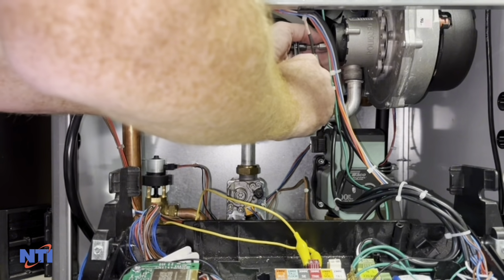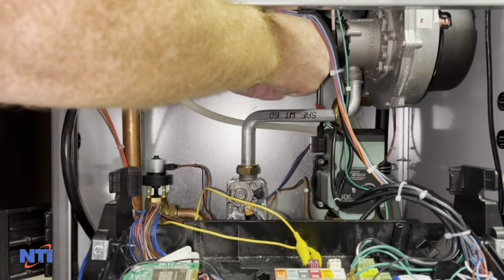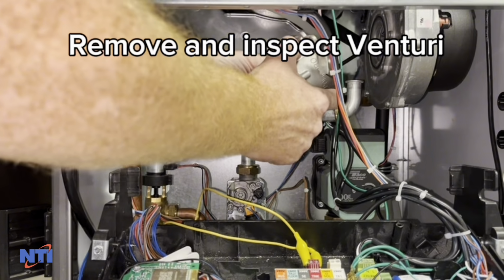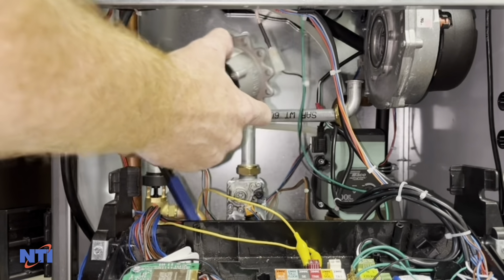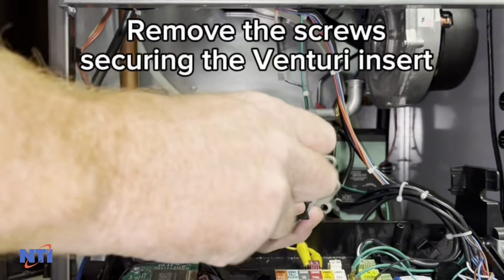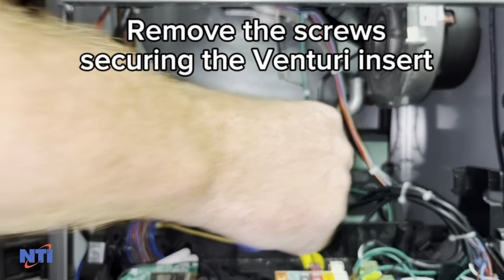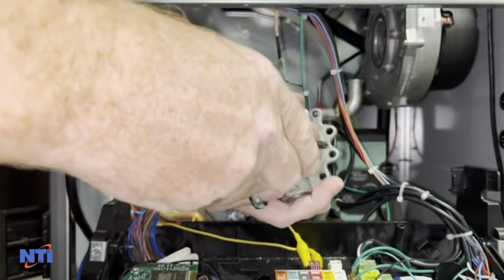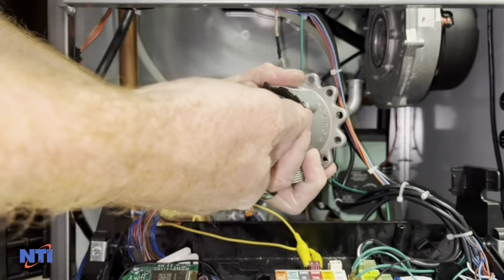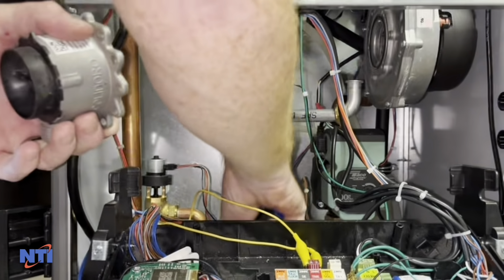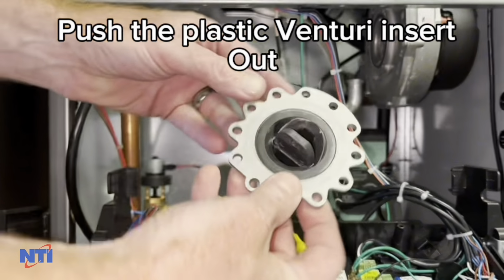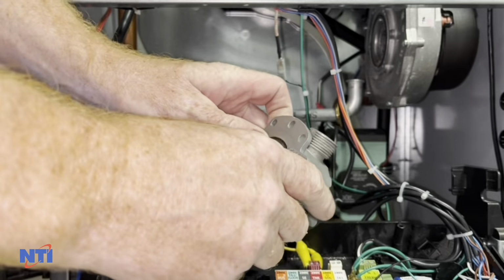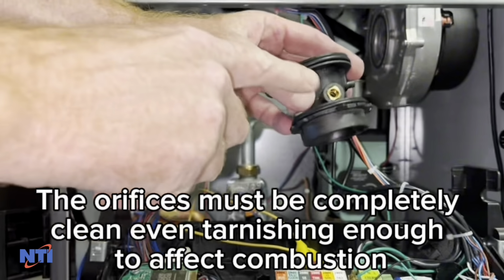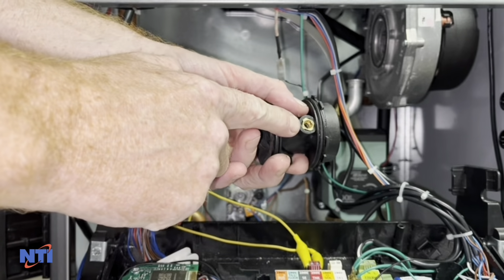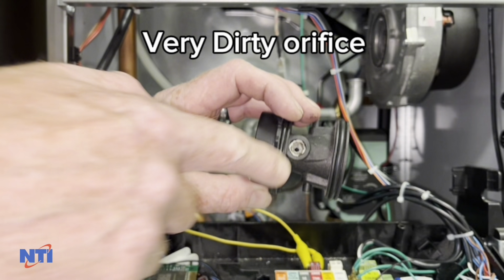After the Venturi is removed, take off the 2 screws that hold the Venturi insert into the aluminum housing. Then, using firm pressure and your thumbs, press the Venturi insert out of the Venturi so the orifices can be inspected. These orifices should be bright and shiny and clean yellow brass or a silver color. Any contamination at all is a reason to replace the Venturi insert.